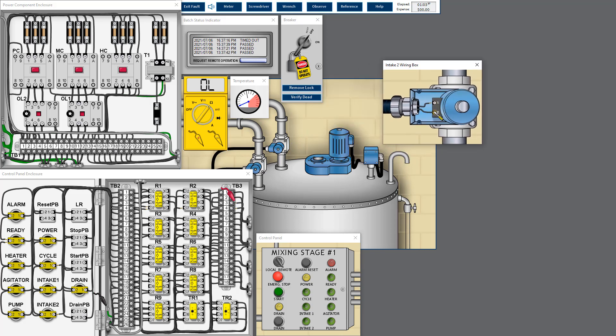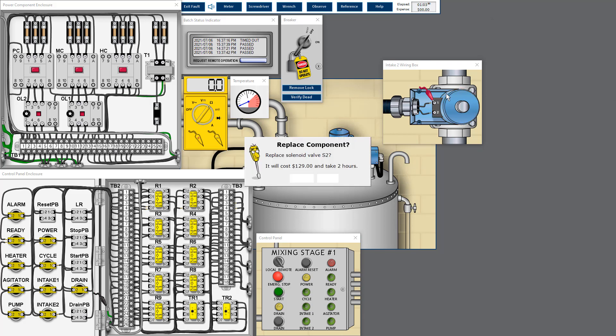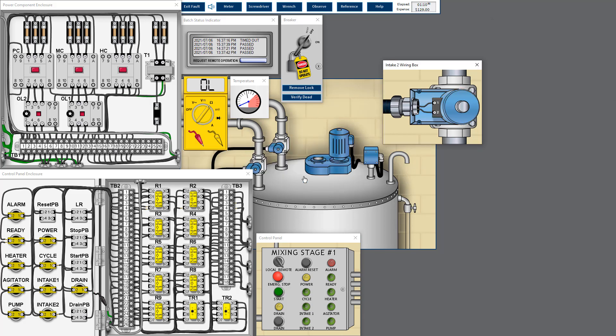I open both ends and double-check — there is a resistance reading confirming the earth fault at the solenoid valve. I need to replace it. After replacement, I measure again — the reading is OL, open circuit, meaning there is no longer an earth fault in the S2 solenoid valve.